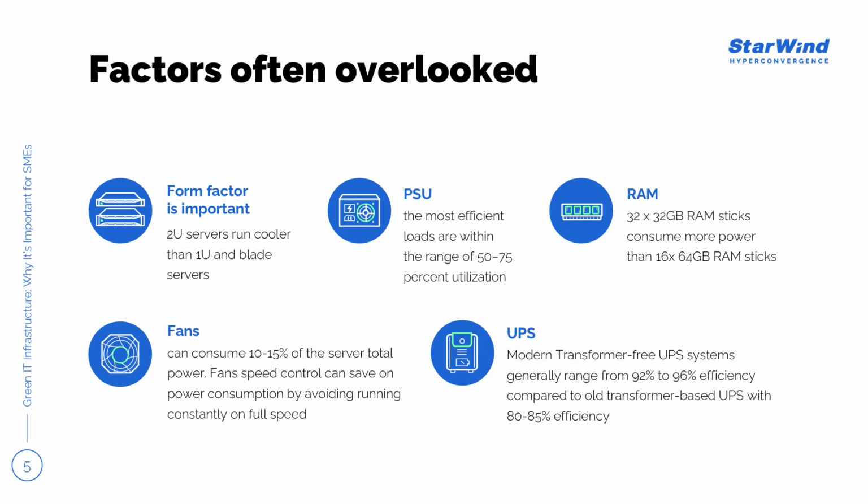The fans themselves can consume 10 to 15% or more of the total power drawn by the server. To improve efficiency, many new servers from major vendors have thermostatically controlled fans, which raise the fan speed as more airflow is needed to cool the server and lower their speed when the components do not heat up as much, basically when you have a lower workload. And correspondingly, these consume less power.